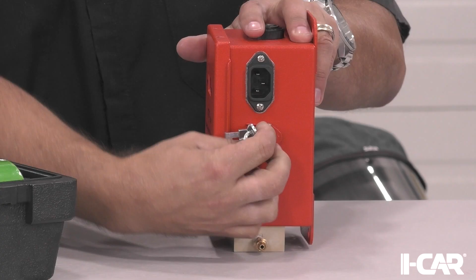The alarm screw sets how high the CO has to be before it alarms. OSHA, or NIOSH, says in automotive body shops it has to be at 10 parts per million or less. So the alarm goes off at 10 parts per million, which is extremely safe.